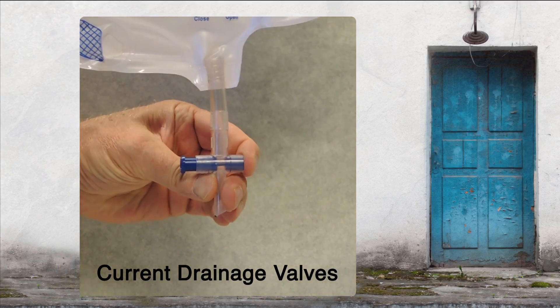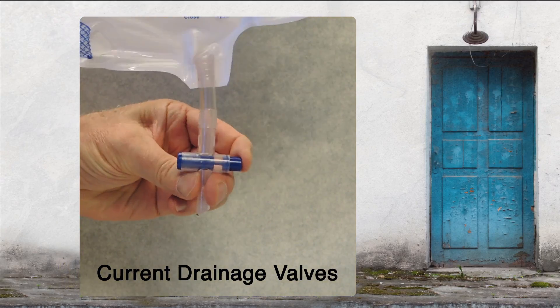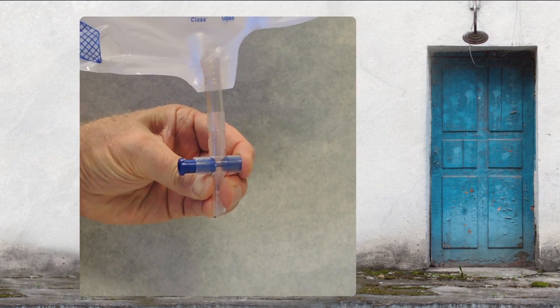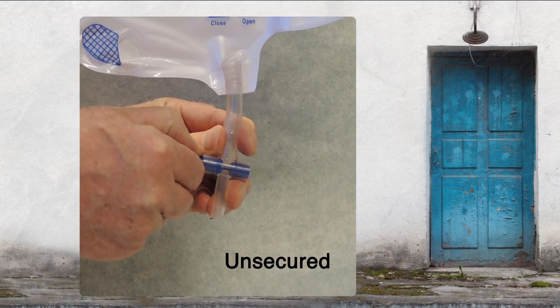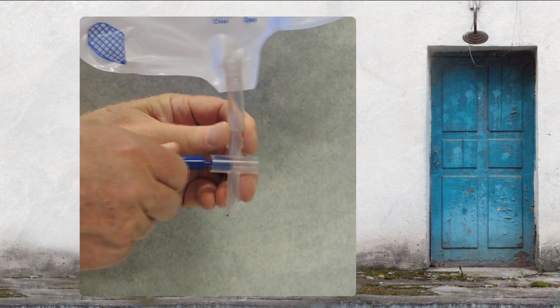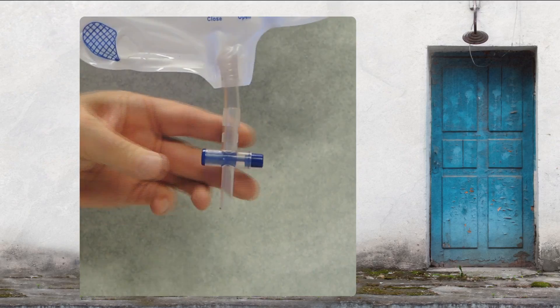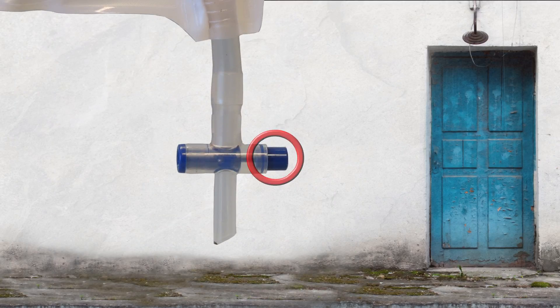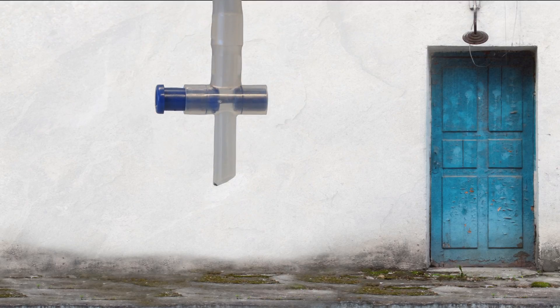Contamination of urine may also occur at the drainage port. Traditional urine collection bags have a sliding valve, components of which are at risk for contamination. The drainage valve is not secured and can easily be removed. Sliding of the valve back and forth potentially drags microbial contamination into the urine flow and back into the bag itself. The one-way urine collection system greatly reduces these risks.